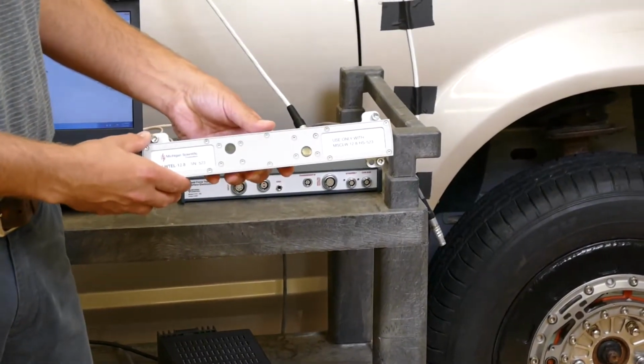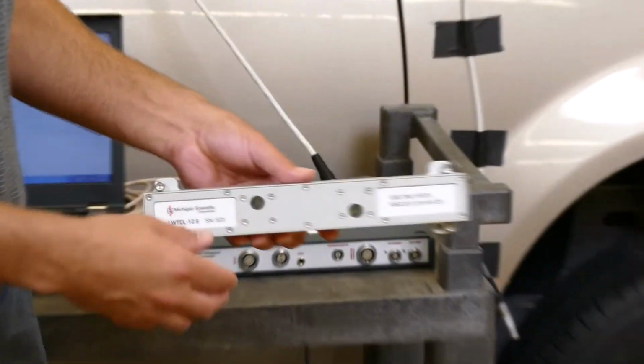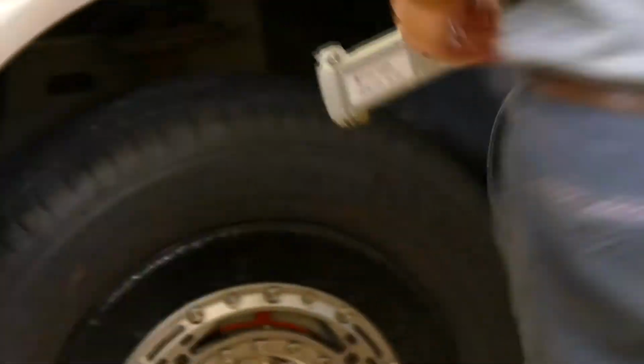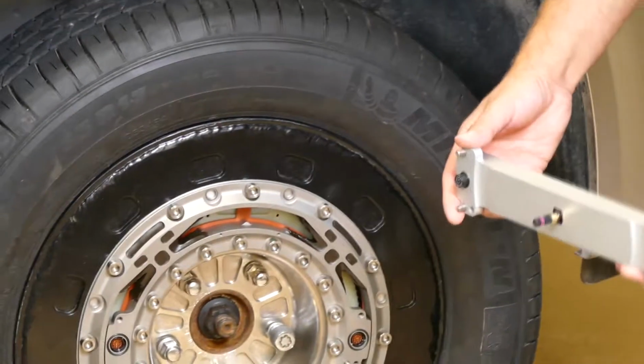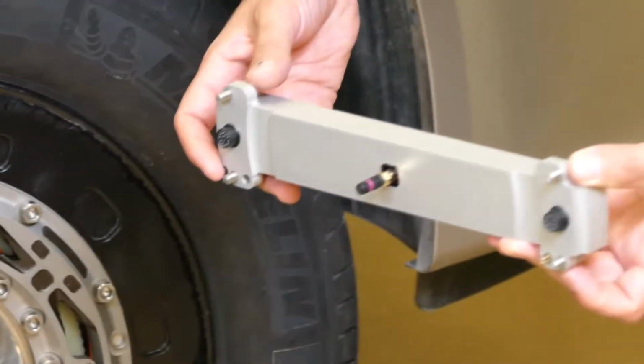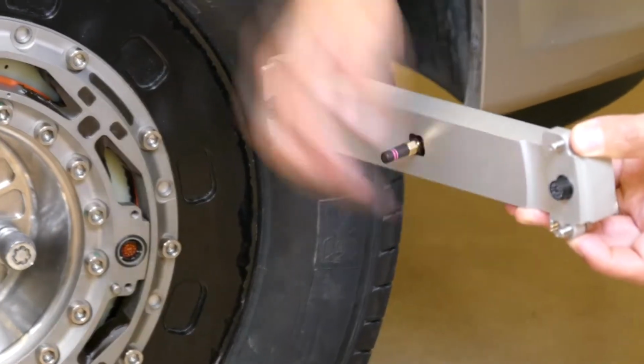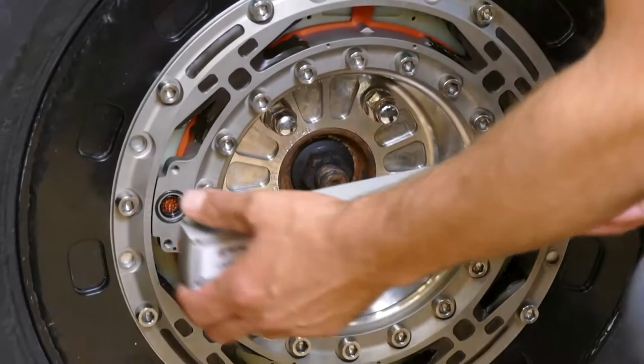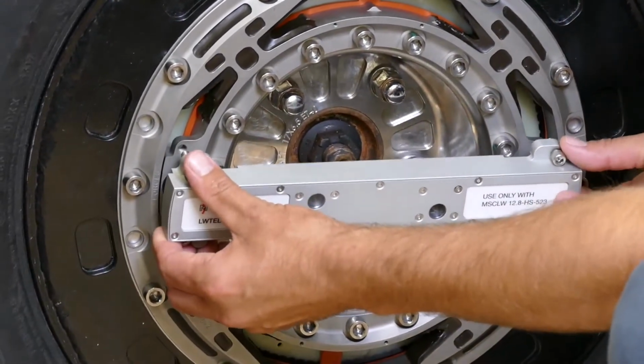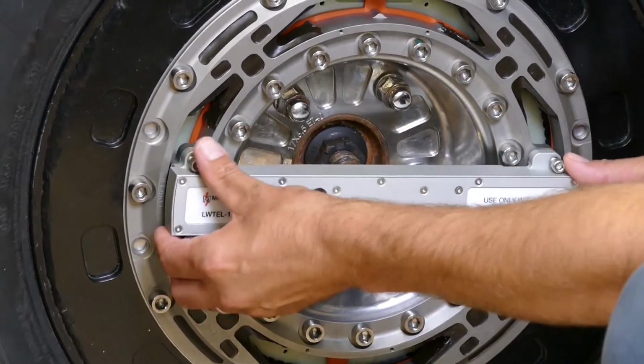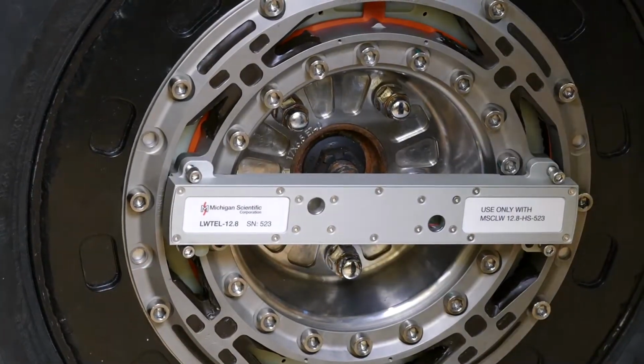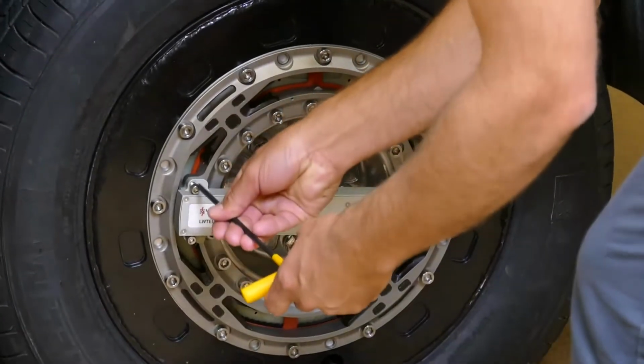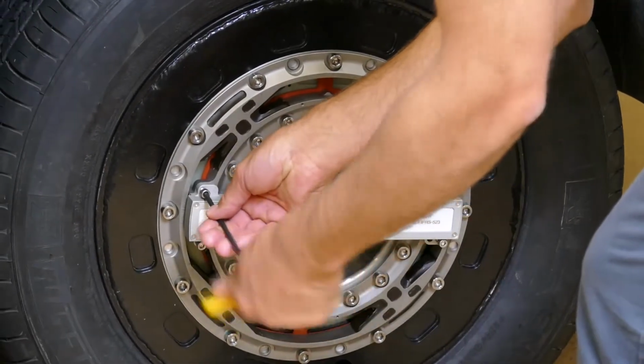So we'll take the telemetry bar and install it to the transducer. We have to carefully check for the dowel pins for both the transducer alignment and for the pin alignment. So find the dowel pins, carefully align them on both sides, press it together. Tighten down the bolts, snug them down now.